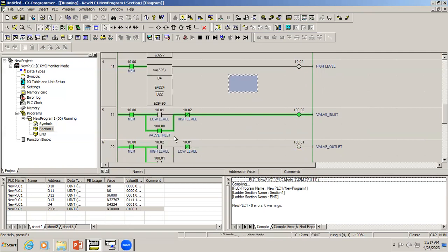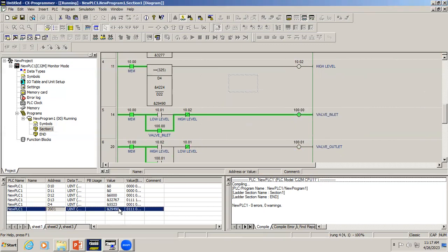Once it reaches the high level, that high level value is 29490, which corresponds to 5400 liters. We are using the greater-than-or-equal-to comparator for that.